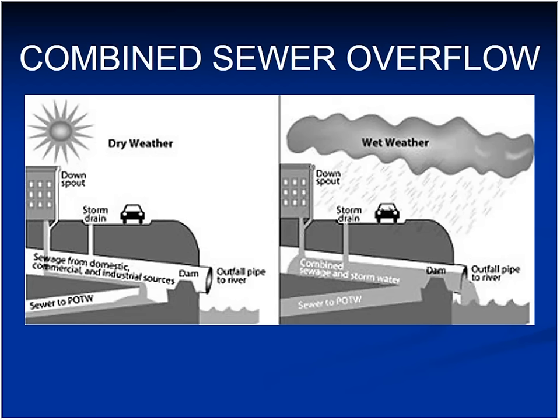In a high flow situation, with a combined sewer overflow, what we see is that in dry weather your collection system is built such that your typical flows will hit some sort of a barrier and continue on to the POTW, the publicly owned treatment works, the treatment plant. But with an extremely high flow, it will allow a certain amount to go straight to the river. Unfortunately, that generally causes all sorts of grief with the residents and shuts down swimming beaches from time to time. For folks in New York State, you're familiar with the Gowanus Canal, which tells you what's happening there. If you ever saw that video, it's really nasty during a combined sewer overflow.